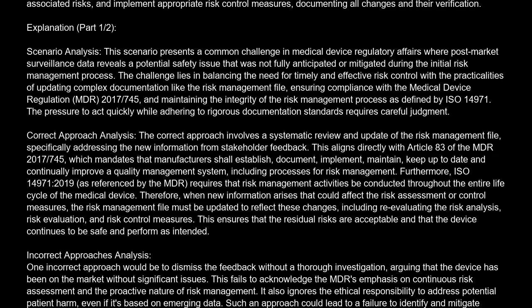The correct answer is B. Immediately update the risk management file to include the identified user interface failure mode, reevaluate the associated risks, and implement appropriate risk control measures, documenting all changes and their verification.